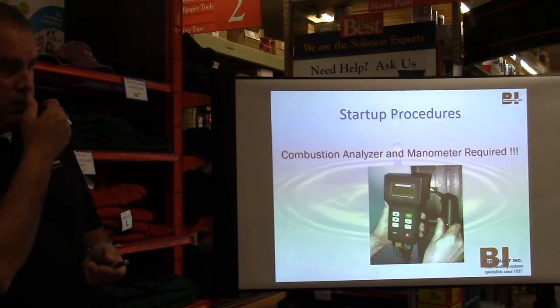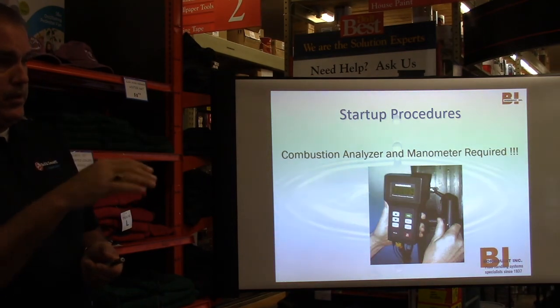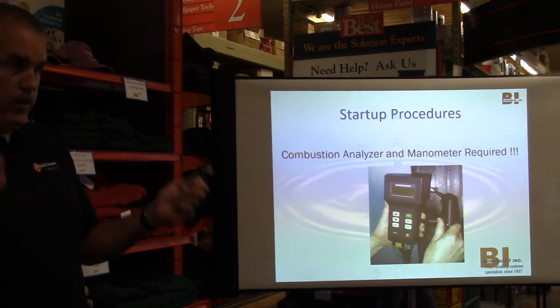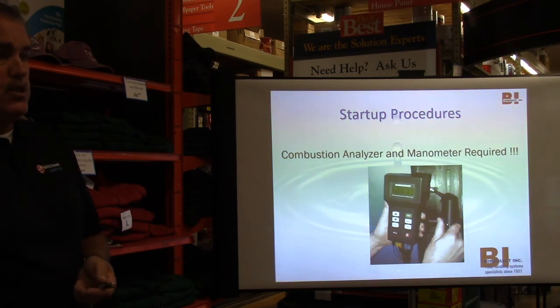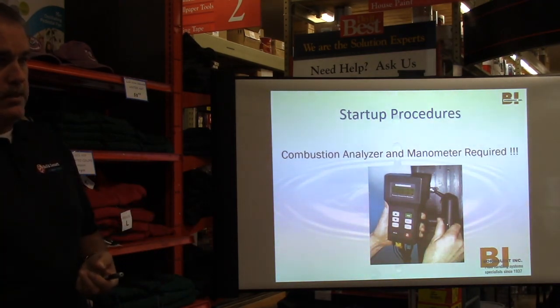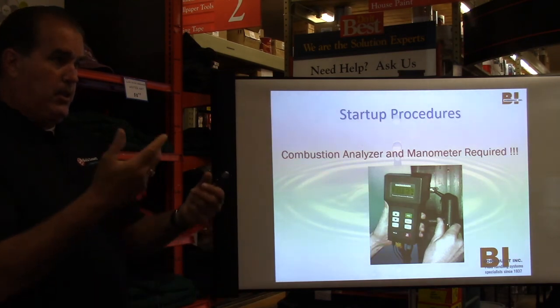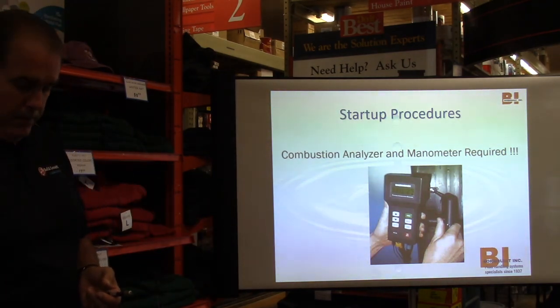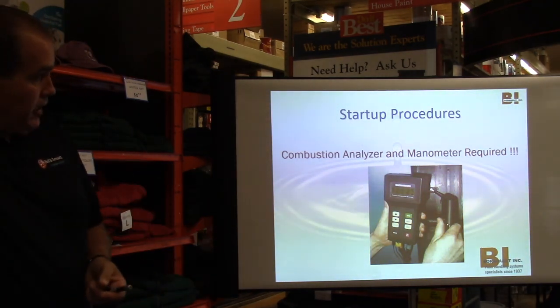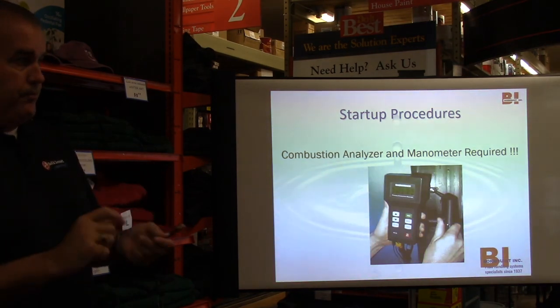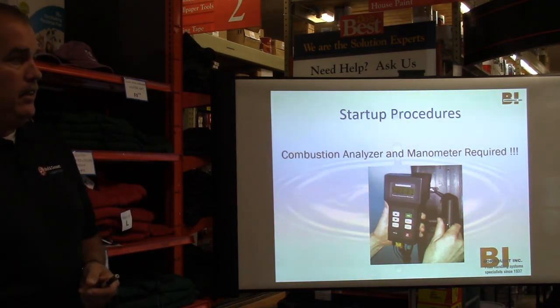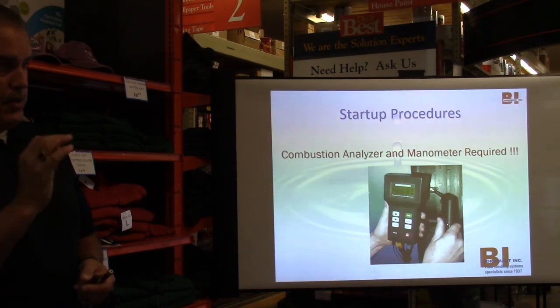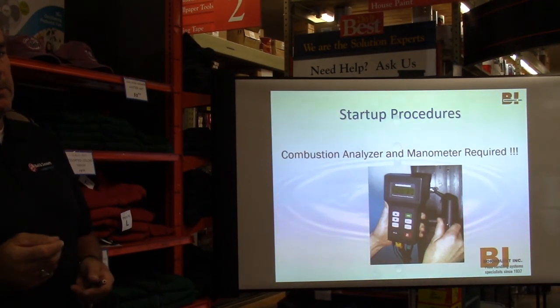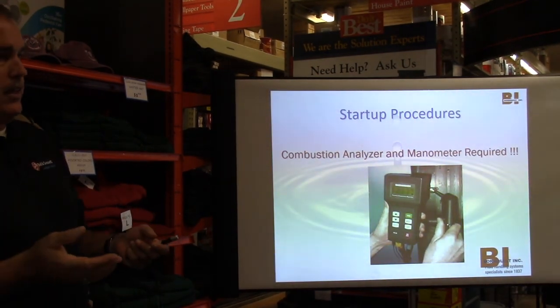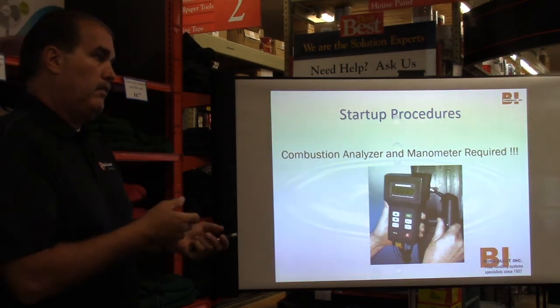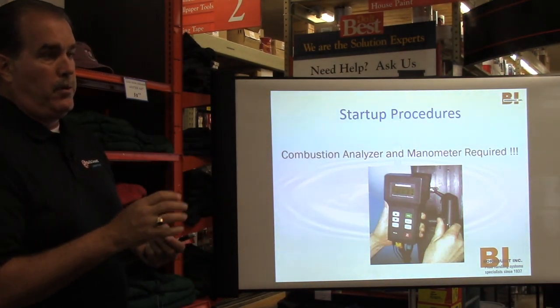On some atmospheric boilers, the only way to adjust that is to clean the burner and clean the heat exchanger to get the air flowing properly, because that's what will change the combustion process, since it just doesn't have the proper mixture of air and fuel for proper combustion. On modulating burners, there are adjustments to the gas and air mixture to precisely tune it in. That's why with a modulating or higher efficiency burner they can get the higher efficiencies, because they can control that burner a lot better.